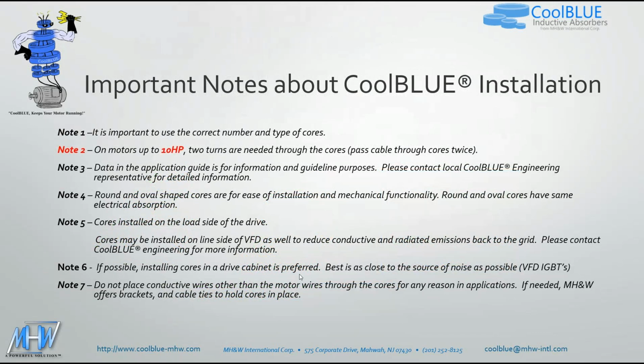So some important notes. It is important to use the correct number and type of cores that's called out on the VFD or on the application guide. One side note, on motors of basically 10 horsepower and below, instead of just placing the wires through the cores, you actually have to run the wires through the cores twice, and basically create two turns through the ID of the core. So you have to put the wire through, loop it around, and put it through again. And that's only on 10 horsepower and below applications. No other application would this be required.